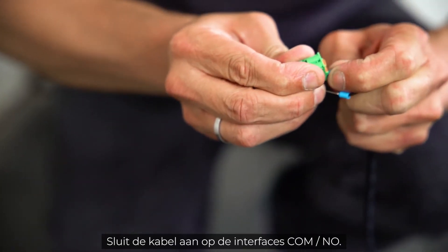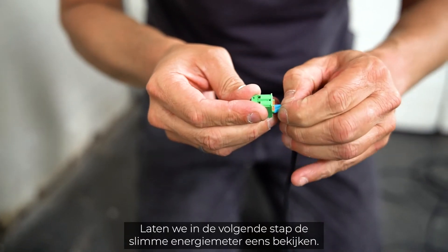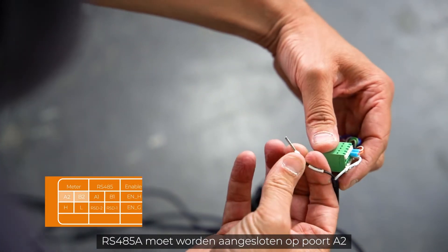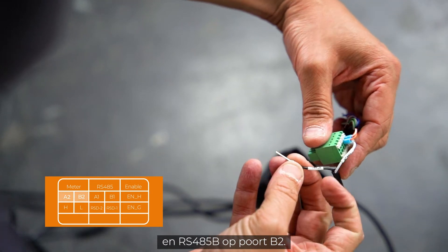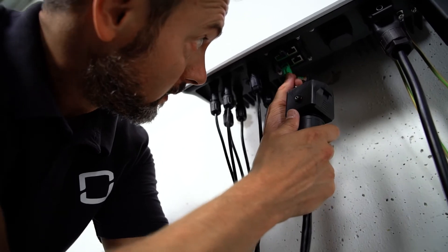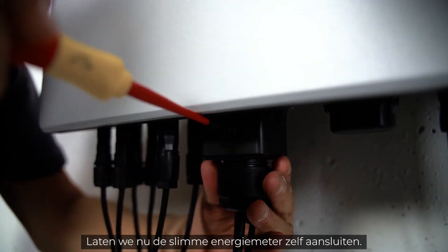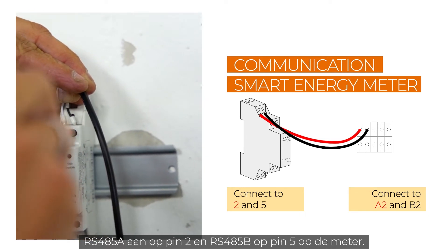If you want to add a heat pump to the system, you also have to connect it via the communication port — connect the cable to the interfaces COM and NO. Now let's have a look at the smart energy meter. RS485A has to be connected to port A2 and RS485B to port B2. Plug everything together and fix it with an M4 screw. Mount the meter on a DIN rail and connect the communication cable RS485A to pin 2 and RS485B to pin 5 on the meter.